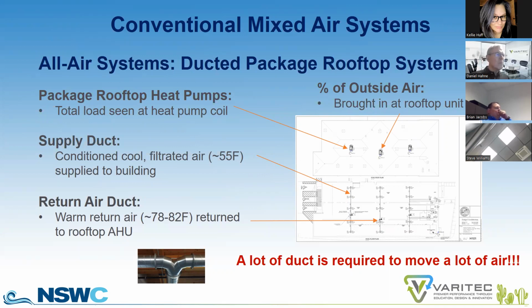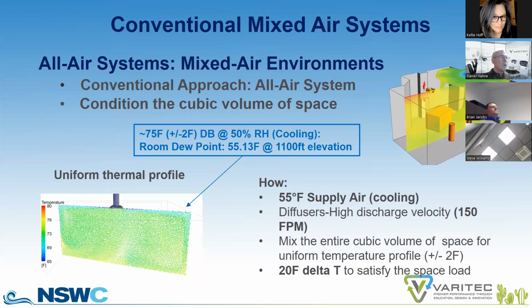But in an all air system, because air is not a dense heat transfer medium, you need a lot of duct work in order to supply that air to a building. And then you condition that building, usually per ASHRAE Standard 55's design guidelines, to a 75-degree temperature at the thermostat. We're seeing some fluctuations now with more efficient buildings, maybe bumping that in summer to 77, 78, and in winter maybe reducing it from 72, maybe down to 70, etc. And we try to maintain a room dew point of 55.13 degrees, which is equal to 50% relative humidity at 75 degrees dry bulb temperature. And air is injected at high velocity into a space at 55 degrees to create uniform mixing in a space.